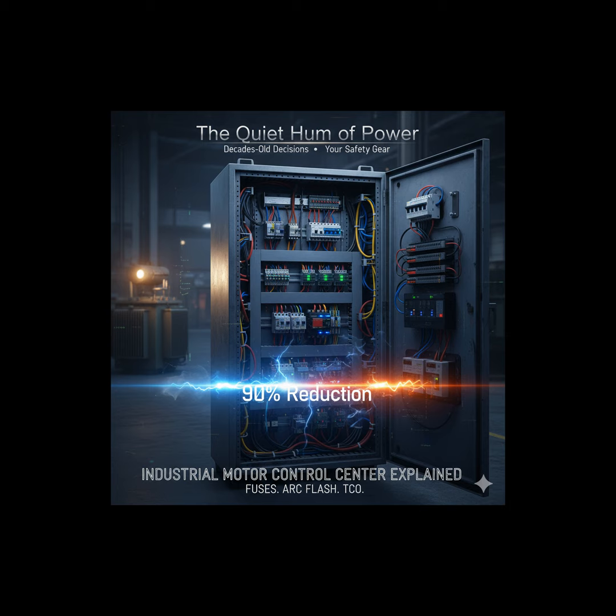Of course. However, the life cycle costs of the breaker system can catch up quickly. NFPA 70B mandates that breaker systems often require complex testing and calibration every 3 to 5 years to ensure they still meet their tripping curves. That's an expensive, dedicated maintenance project. And you have to factor in the PPE. You do. When you factor in the significantly higher cost and logistics of providing that high-category arc flash PPE for all personnel servicing the higher-risk breaker system, the TCO can actually swing back to favor the fuse system, despite the replacement cost. It forces a tough choice between immediate downtime and long-term safety and compliance costs.